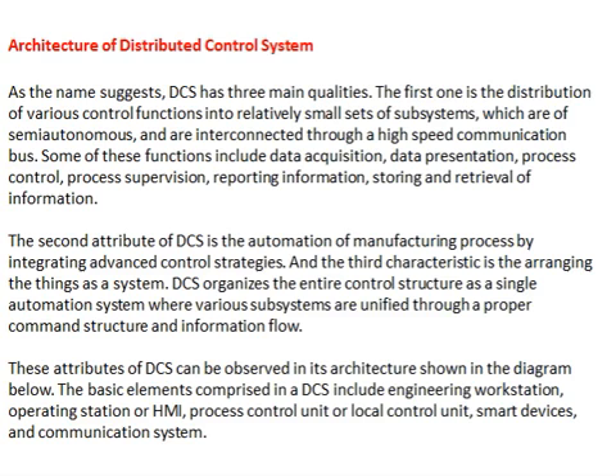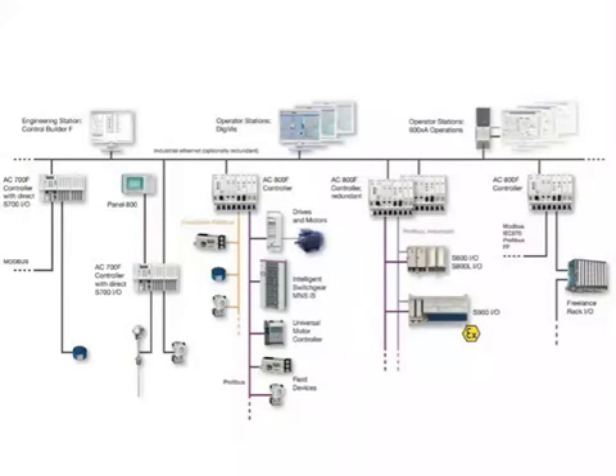The second attribute of DCS is the automation of the manufacturing process by integrating advanced control strategies. And the third characteristic is arranging the things as a system. DCS organizes the entire control structure as a single automation system, where various subsystems are unified through a proper command structure and information flow. These attributes of DCS can be observed in its architecture shown in the diagram below. The basic elements comprised in a DCS include engineering workstation, operating station or HMI, process control unit or local control unit, smart devices, and communication system.